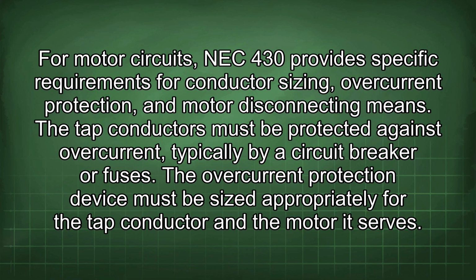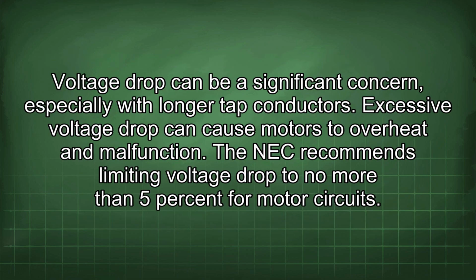For motor circuits, NEC 430 provides specific requirements for conductor sizing, overcurrent protection, and motor disconnecting means. The tap conductors must be protected against overcurrent, typically by a circuit breaker or fuses. The overcurrent protection device must be sized appropriately for the tap conductor and the motor it serves. Voltage drop can be a significant concern, especially with longer tap conductors. Excessive voltage drop can cause motors to overheat and malfunction. The NEC recommends limiting voltage drop to no more than 5% for motor circuits.